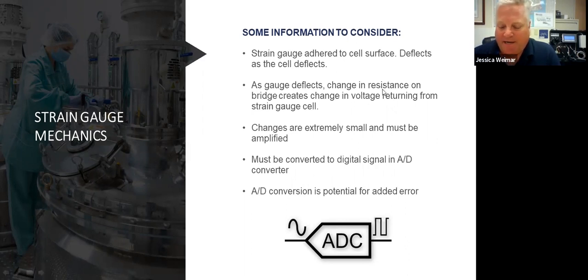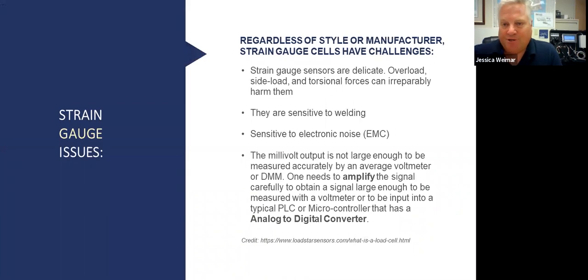The strain gauge unit, as it moves, creates very small changes in voltage, and that means that the change has to be amplified in order to travel to the converter. And also, in a strain gauge load cell, that's an analog signal. It's a resistance change, which is an analog signal, and it needs to be converted to a digital signal within the converter before it can be read by the system. So a couple of things to think about with a strain gauge.